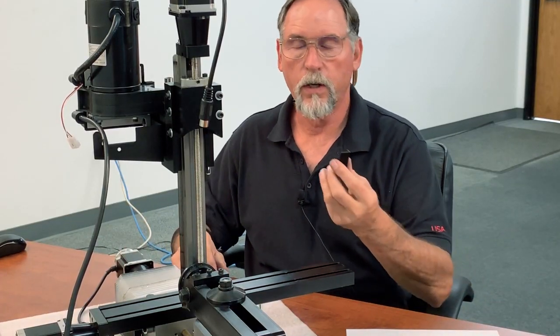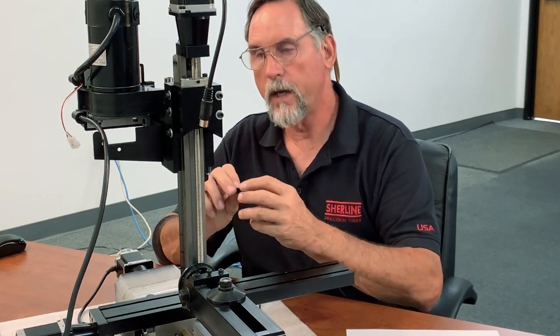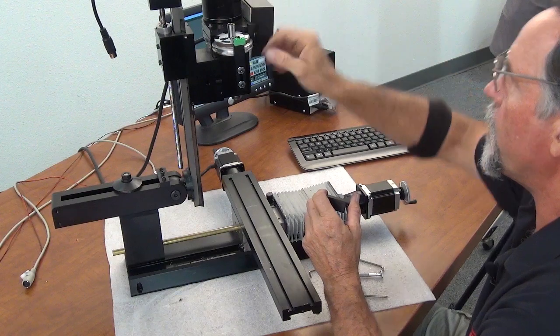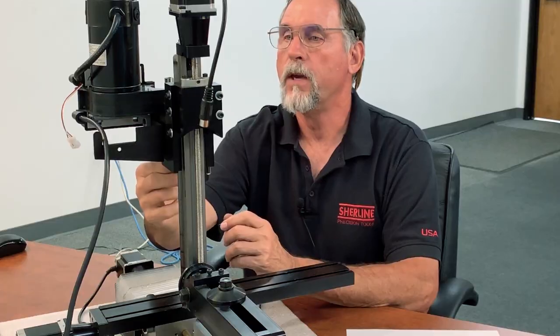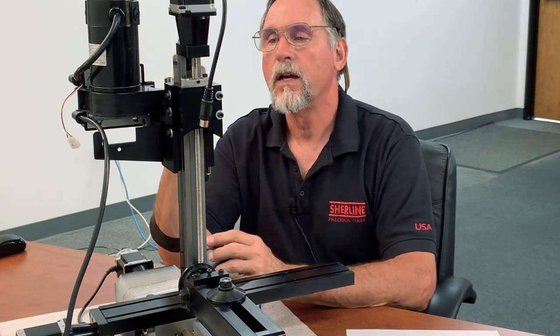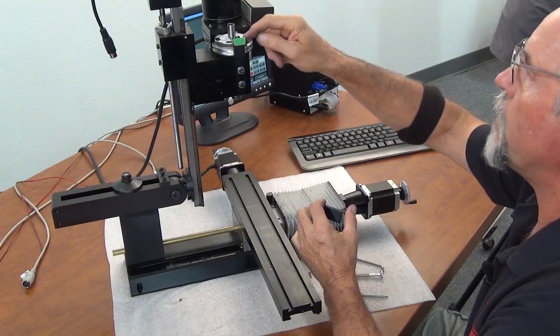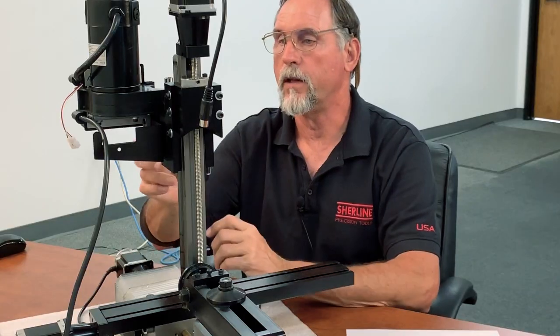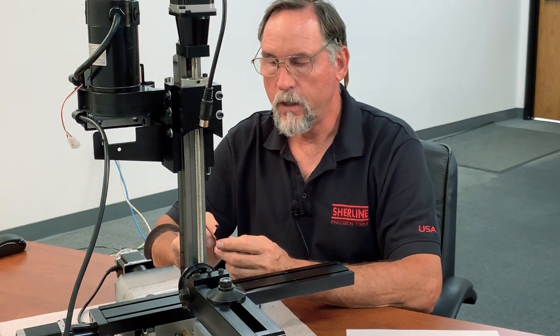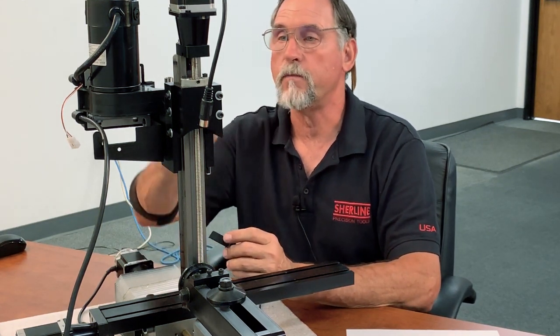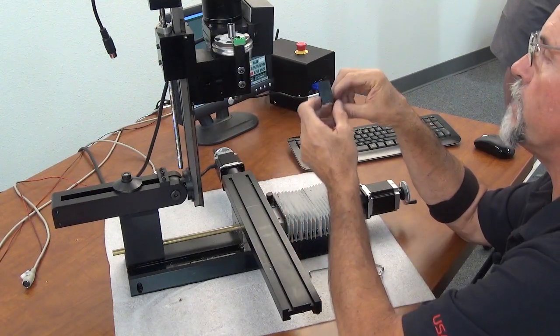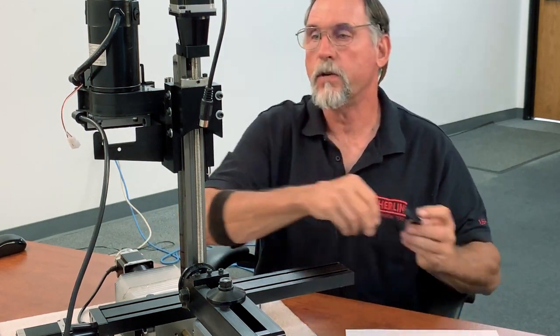Now, the next thing we're going to put on is the optical encoder cover. What we found out the hard way was if you're in a room where the overhead lighting is fluorescent, then there's not going to be any light interference with the optical encoder. However, the optical encoder has three LED lights that shine down onto the label, and then the light bounces back up. If you have LED lighting, which we put in recently for energy saving, or you have any LED lights in the area, that LED light, the outside LED light, will reflect off of this, and your optical encoder will start giving you a bad reading. The RPMs will either jump around, or if you're doing single point threading, you're going to start cross-threading because it's getting bad signals off of your tach sticker. The cover is, first and foremost, to protect the optical encoder from any chips or anything that comes off of the work that you're doing, and secondly, to get rid of any exterior LED light interference.